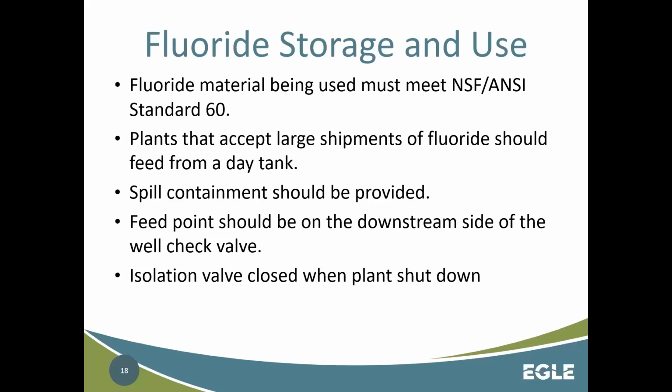All right, just some fluoride storage and use best practices. So again, if you are applying any chemical to your drinking water, it has to meet NSF/ANSI Standard 60. Plants that accept large shipments of fluoride should feed from a day tank, and that's of course to prevent overfeeds, because we don't want to exceed that maximum contaminant level of fluoride in the water that our customers are drinking. So we recommend day tanks for fluoride. It should be about a 24-hour supply.